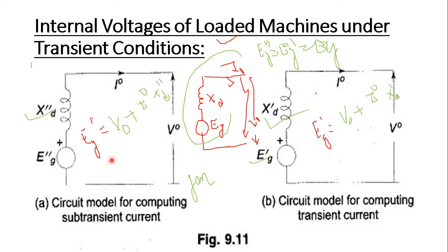So whenever we are dealing with the short circuit of an interconnected system, the synchronous machine, which can be a generator or a motor, can be replaced by its corresponding circuit model, that is, the generated EMF in series with the reactance. That is the corresponding circuit model for the generator and motor, having the voltage behind the subtransient or transient reactance, and the rest of the network is unchanged.